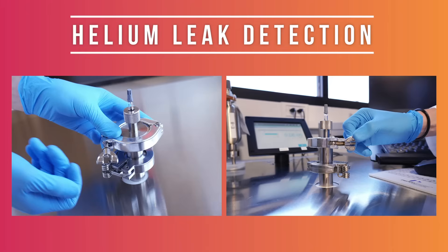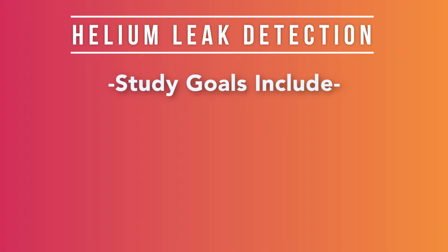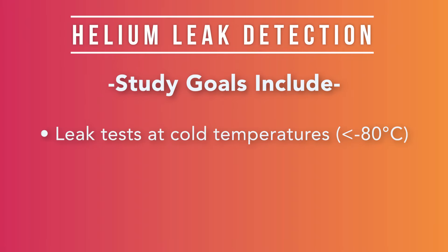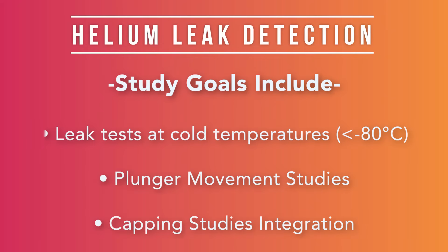Its sensitivity allows for testing to the maximum allowable leakage limit of most products, and its flexibility enables numerous study goals including leak testing at cold temperatures down to negative 80 degrees Celsius or lower, plunger movement studies, and integration into capping studies.